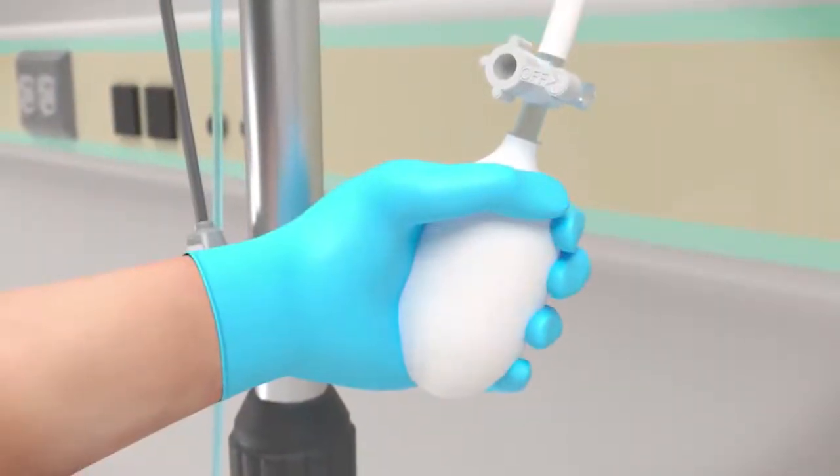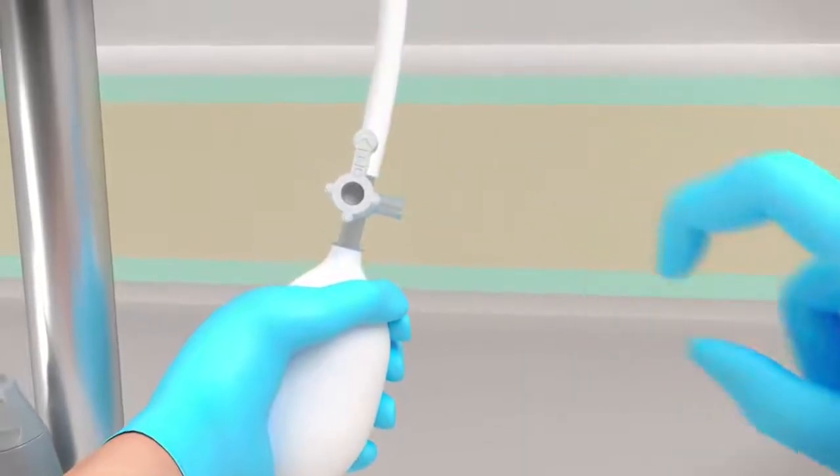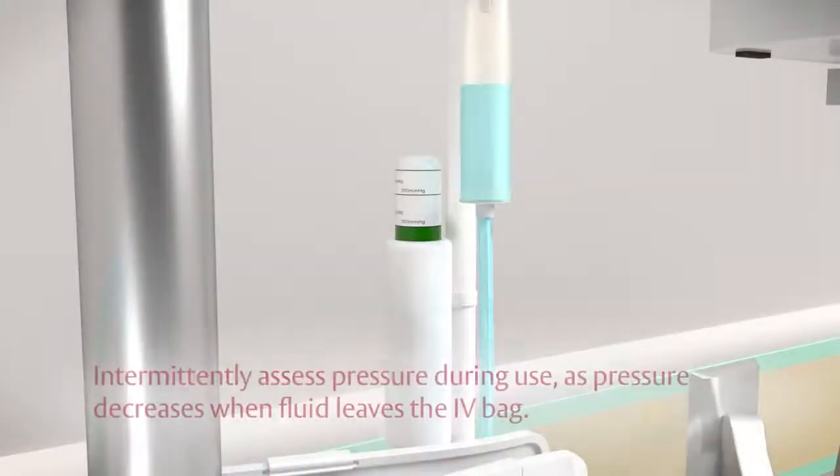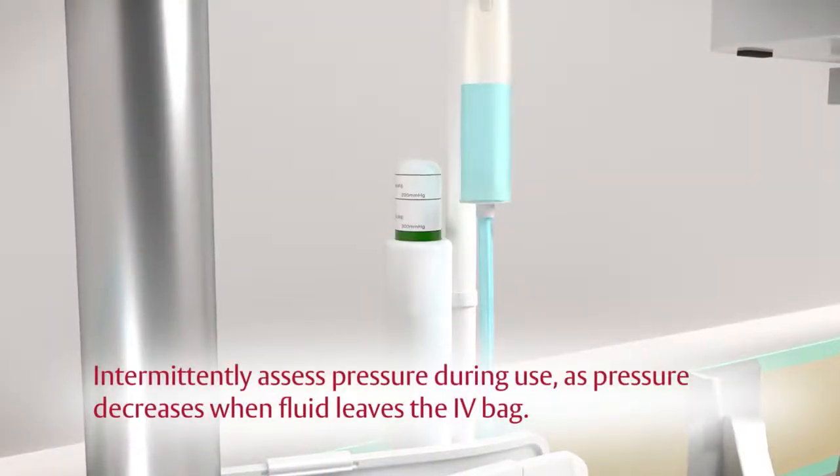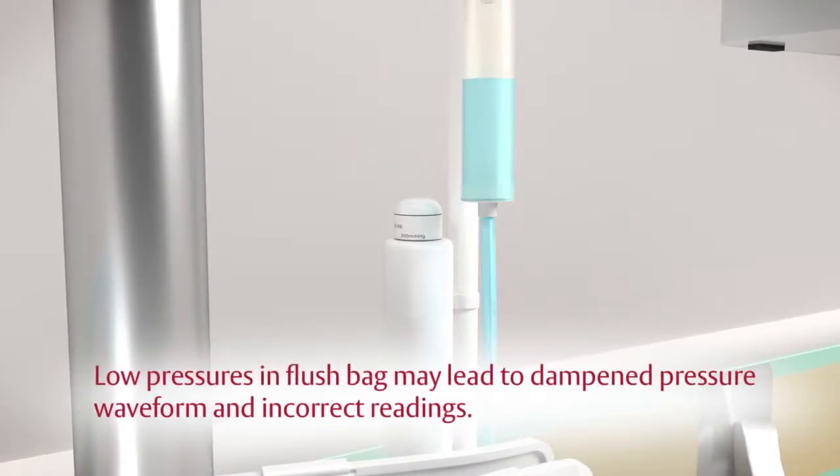Pressurize the IV flush solution bag to 300 millimeters of mercury. Turn stopcock toward the pressure bag to lock off air pressure. Intermittently assess pressure during use as pressure decreases when fluid leaves the IV bag. Low pressures in flush bag may lead to dampened pressure waveform and incorrect readings.